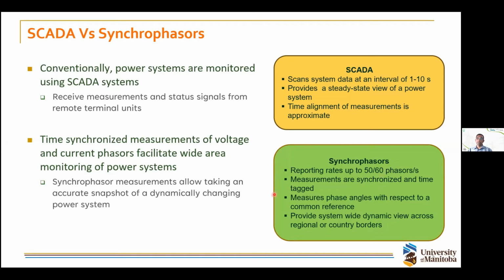The main thing is that the measurements are time synchronized, and each measurement is time tagged. So once you receive the data at a central point, regardless of any communication delays, you can time align all the measurements based on the time stamp, giving you a very accurate snapshot of the whole power system.